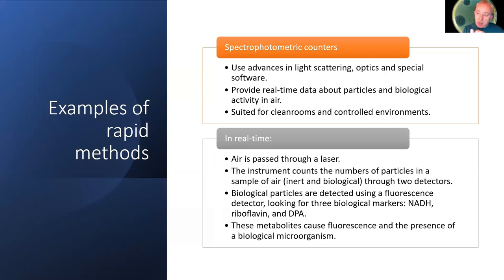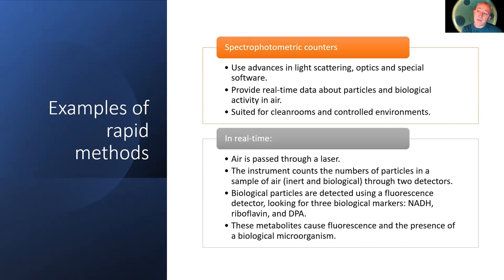Spectrophotometric counters are one example of a rapid microbiological method. These are based on advances in light scattering and optics using special software and sensors. These counters can tell us whether the particles in the air are inert or biological, by looking for markers like NADH, riboflavin, and also DPA — the acid that helps form bacterial spores. If these metabolites are present, they fluoresce and you get additional readings. This is the kind of technology giving us greater knowledge about our levels of control.